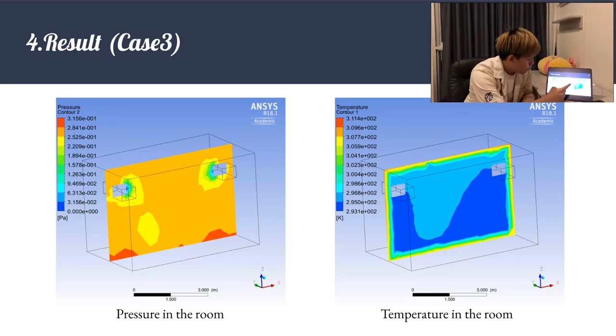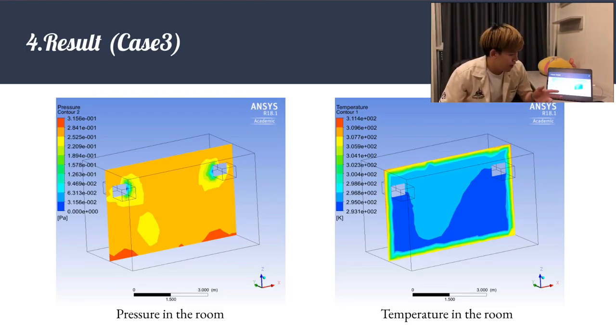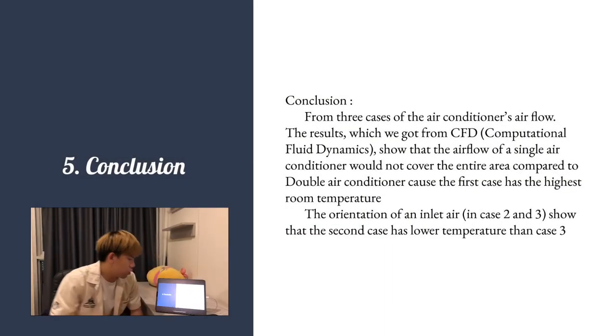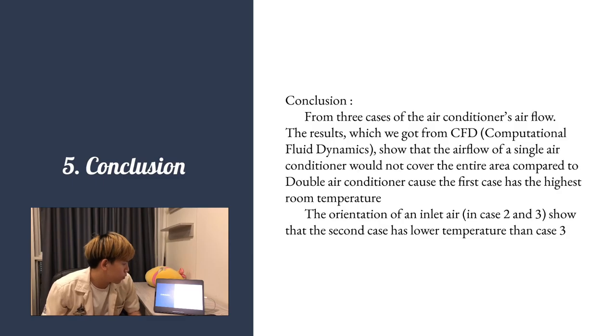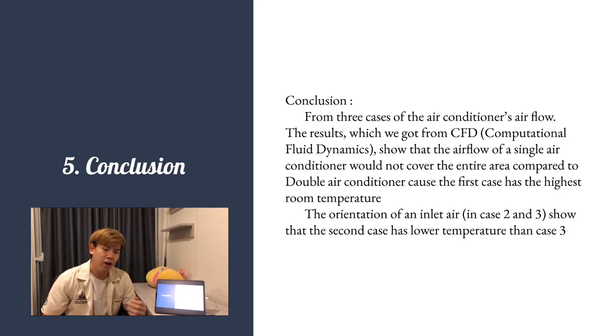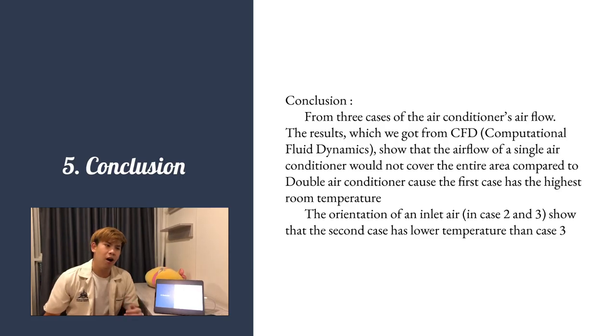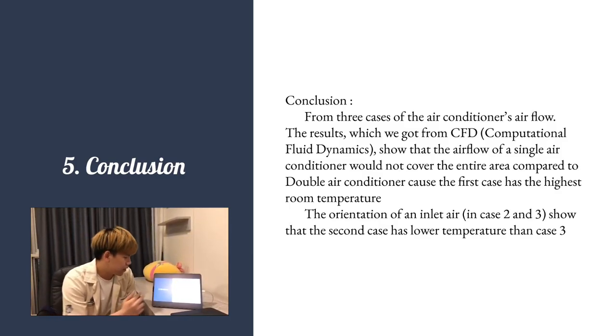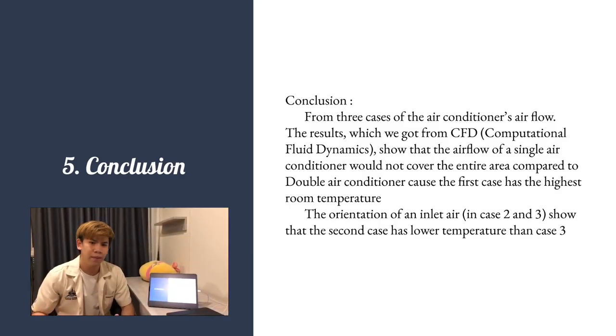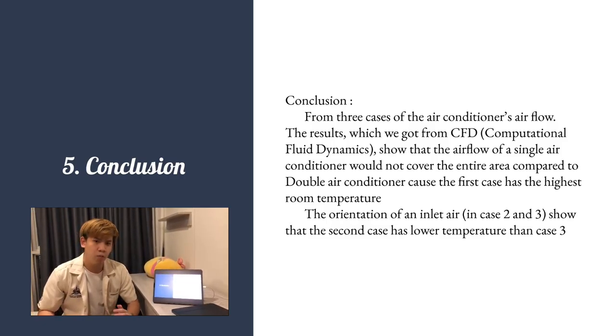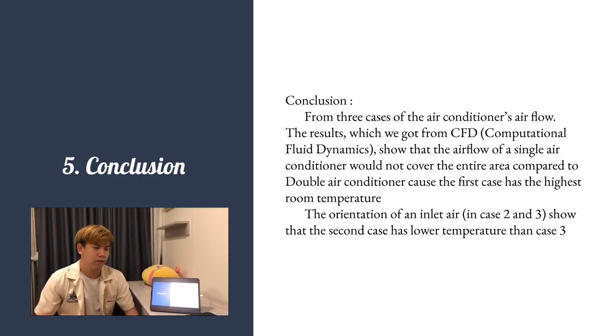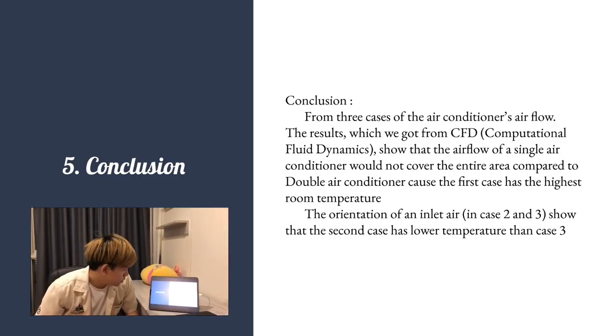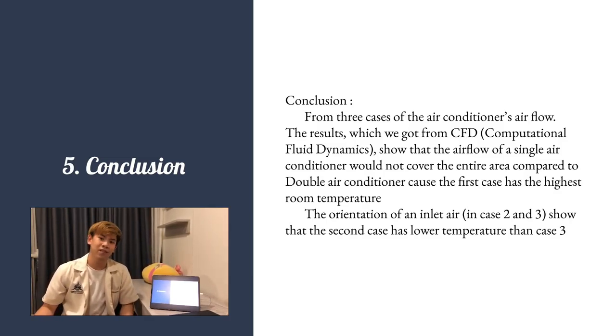To conclude from the three cases, Case 2 is the best configuration to cool the entire room. Case 1 cannot cover all the area, and in Case 3 the temperature is not uniform throughout the room. Therefore, Case 2 with two opposing air conditioners is the best placement.